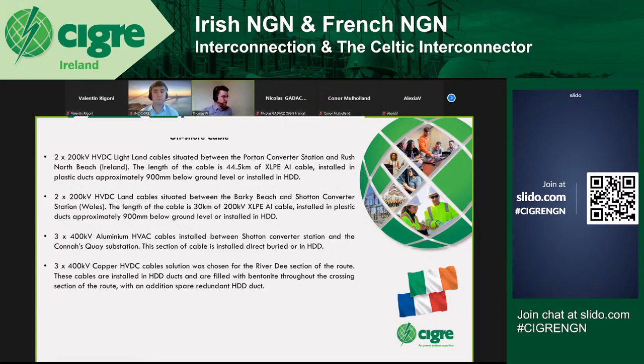From there, we have three 400 kilovolt aluminium HVAC cables installed between Shotton converter station and the Connah's Quay substation, direct buried. We then have a three 400 kilovolt copper HVDC cable solution for a river crossing section across the River Dee, installed in ducts filled with bentonite, with an additional spare duct installed there also.